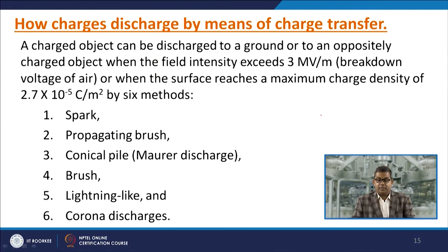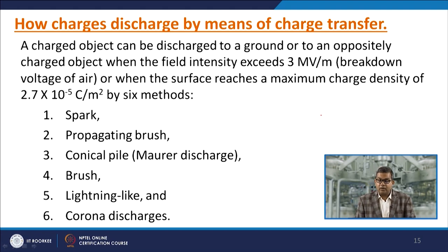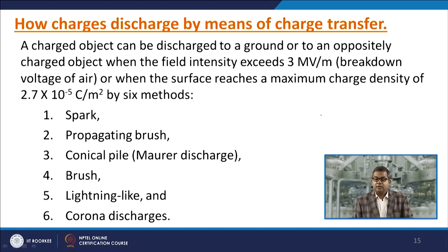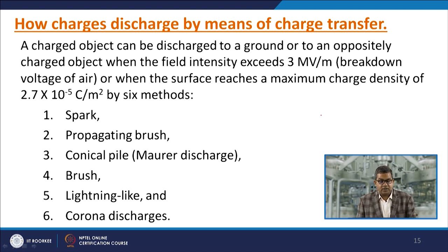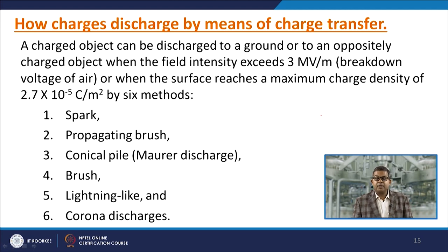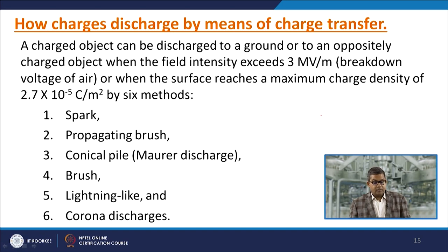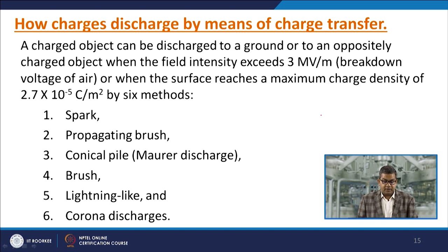A charged object can discharge to ground or to an oppositely charged object when field intensity exceeds 3 megavolts per meter — the breakdown voltage of air — or when the surface reaches maximum charge density. There are six discharge methods: spark discharge, propagating brush discharge, conical pile discharge, brush discharge, lightning-like discharge, and corona discharge.